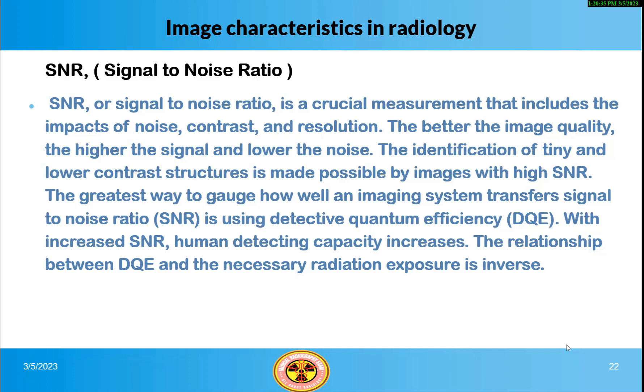SNR, or signal-to-noise ratio, is a crucial measurement that includes the impacts of noise, contrast, and resolution. The better the image quality, the higher the signal and lower the noise. The identification of tiny and lower contrast structures is made possible by images with high SNR. The greatest way to gauge how well an imaging system transfers SNR is using Detective Quantum Efficiency (DQE). With increased SNR, human detecting capacity increases. The relationship between DQE and the necessary radiation exposure is inverse.